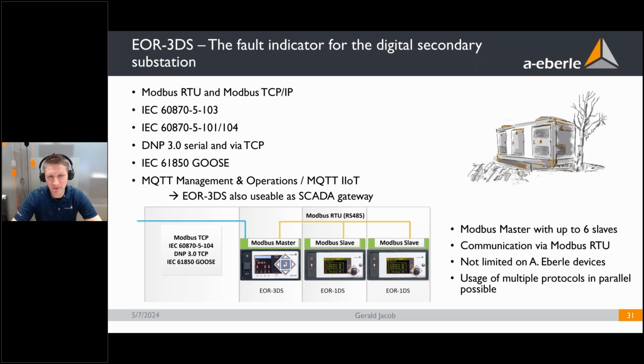And one new piece of information is that you can use the EOR-3DS as a SCADA gateway via Modbus RTU. This is not limited to our Eberle devices. You can also use other devices, but here in the example, you can see EOR-1DS devices, for example, in cable fields 2 and 3. They are read out via Modbus, acting as Modbus slaves, and are read out from the EOR-3DS, which acts as a Modbus master. So all the information is transferred to the EOR-3DS and can then be sent directly via another protocol, for example, Modbus TCP or 104 protocol, to the central SCADA system.